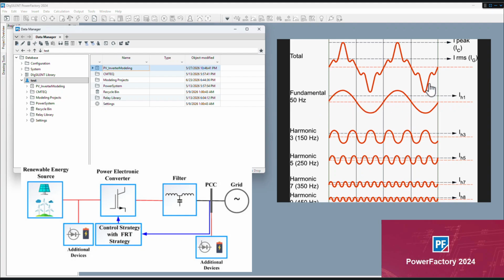Now, because we need to fight these harmonics whenever they stick their head into our power system networks, many studies have been conducted to assess power system harmonics, and such studies have resulted in the creation of standards such as the IEEE 519, which we use to assess power system harmonics in this tutorial. This standard, the 519, specifies recommended harmonic limits for your power system network at every voltage level, to ensure that there is acceptable power quality.